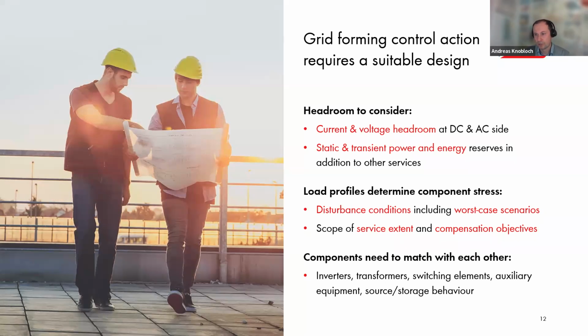Suitable design is also required because load profiles determine the component stress. So you might have very high disturbance conditions at the point of connection of your power plant that provides grid forming services. And here, the load stress will depend on one side on the worst case scenarios that you would like to ride through in a grid forming manner with maximum support. And on the other side, also on the scope of service extent. So on how much grid forming service you would like to provide on your compensation objectives.